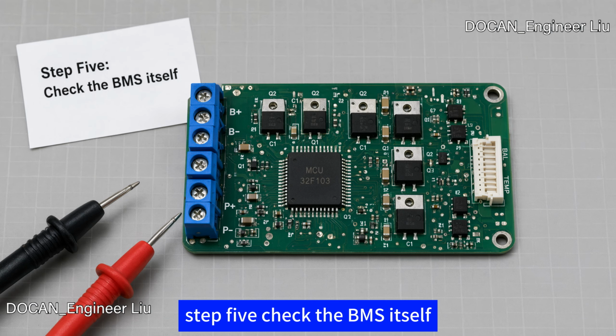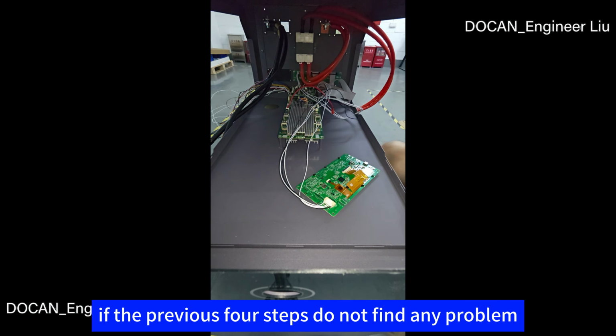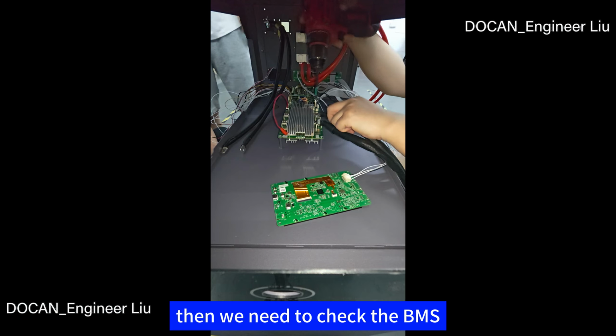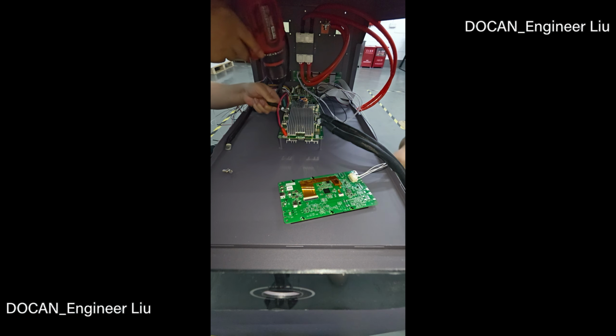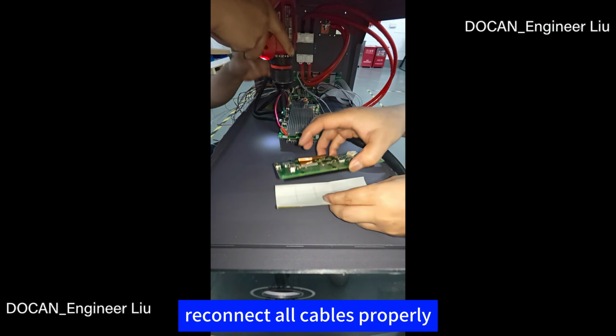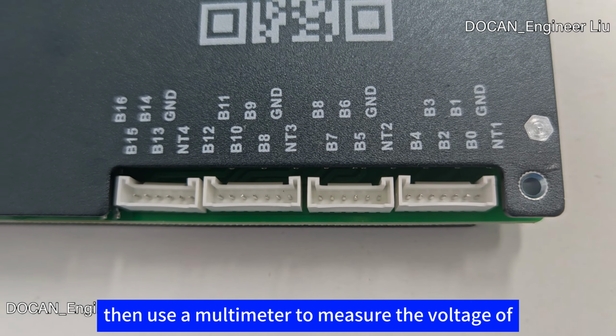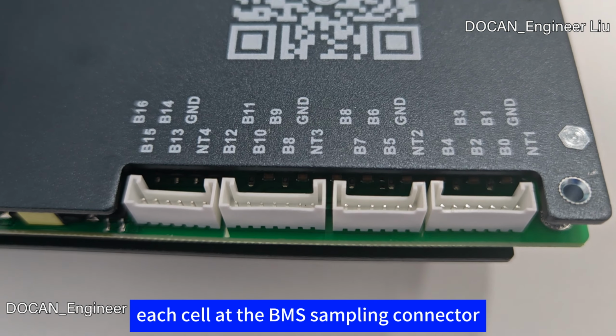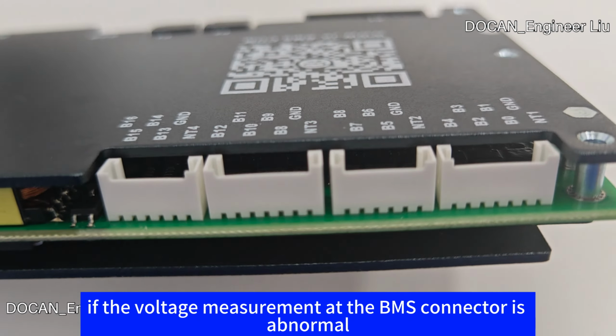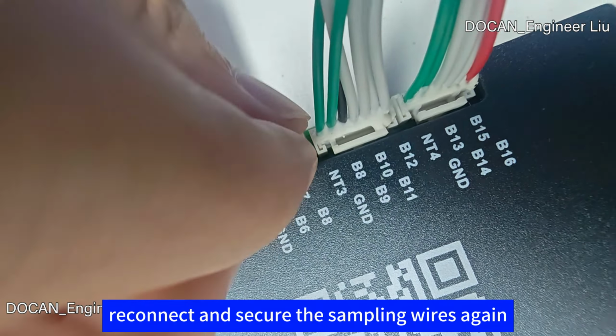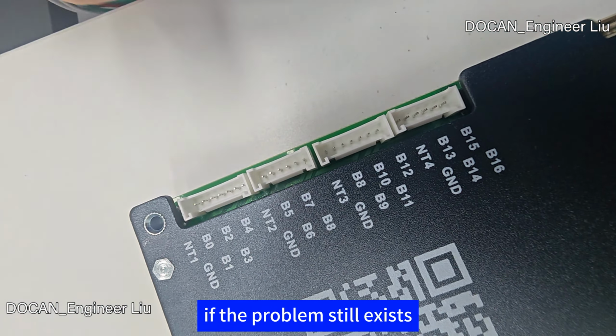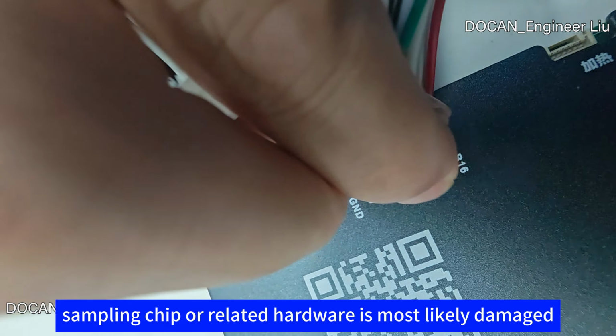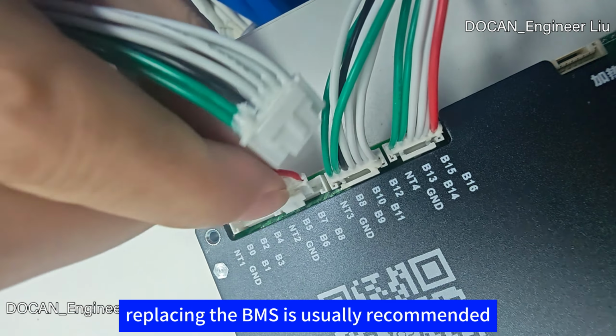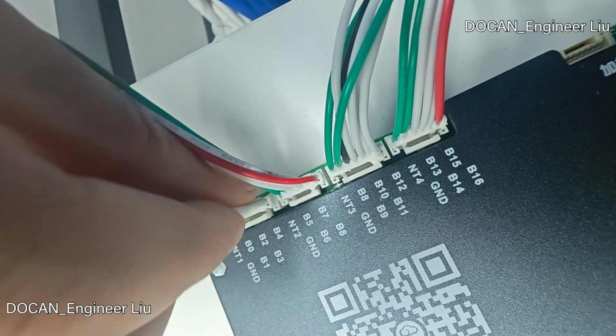Step 5, check the BMS itself. If the previous 4 steps do not find any problem, then we need to check the BMS. Reconnect all cables properly. Then use a multimeter to measure the voltage of each cell at the BMS sampling connector. If the voltage measurement at the BMS connector is abnormal, reconnect and secure the sampling wires again. If the problem still exists, then the BMS sampling circuit, sampling chip, or related hardware is most likely damaged. In this situation, replacing the BMS is usually recommended.